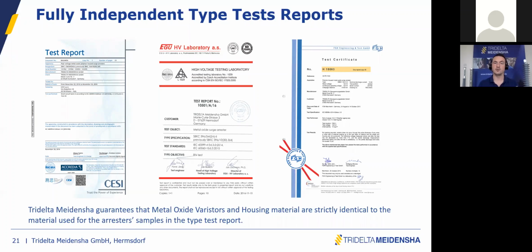For example, if you look at a Tridelta test report, you will see that the type of MOV which is used is clearly written on the report. Also, if you go to CESI for a short circuit test, and if you fail the test and you have to repeat it, you're going to see it in the report. You're not going to see only the test that has been passed. So these things, I think, are important when it comes to independence of a test lab.